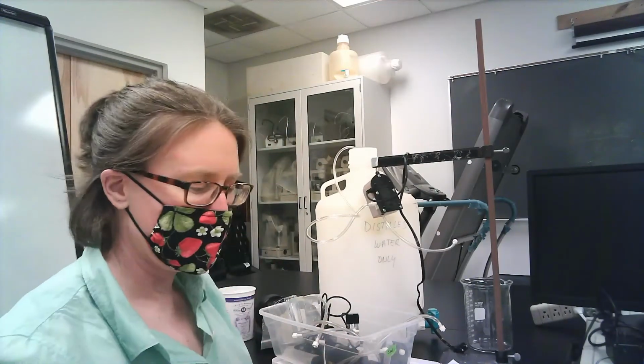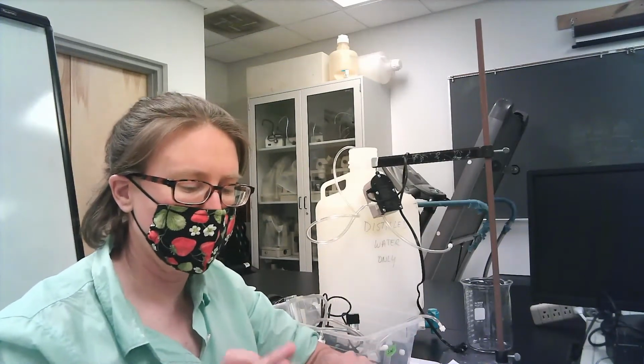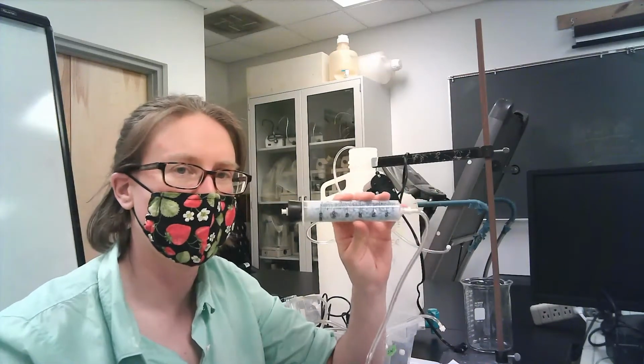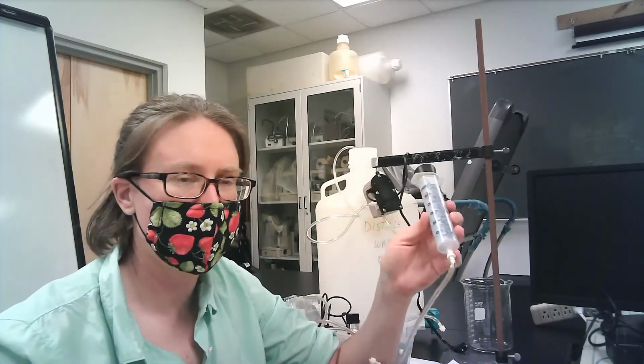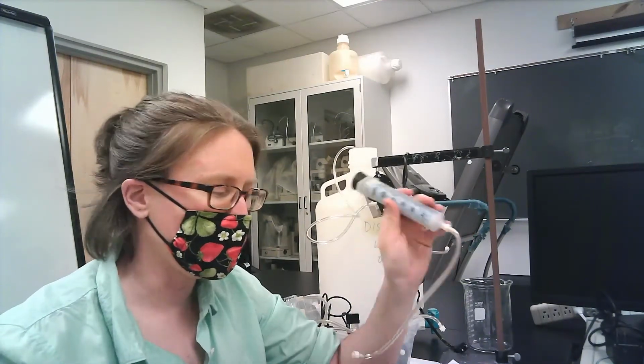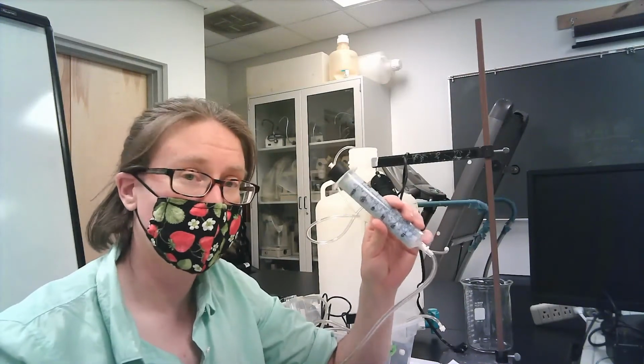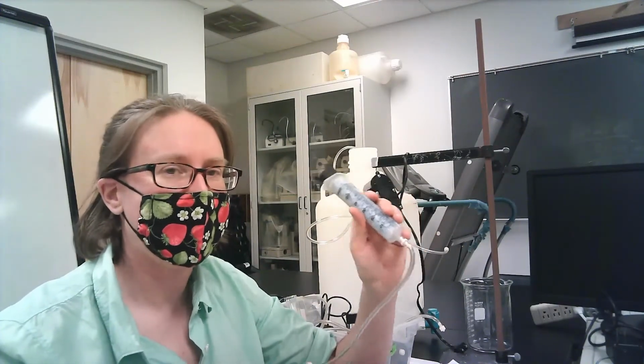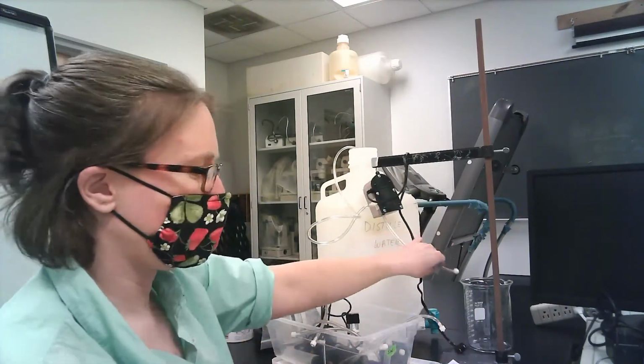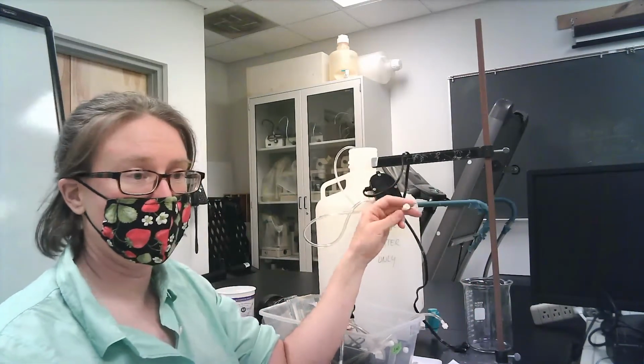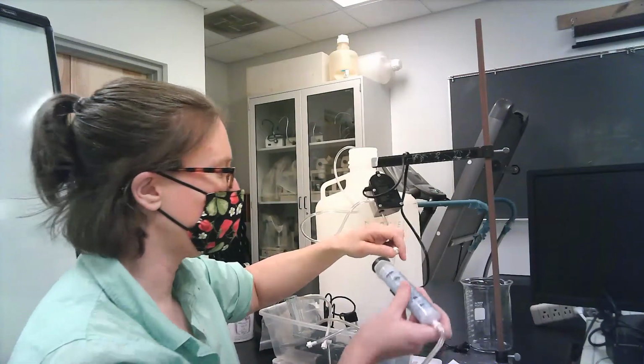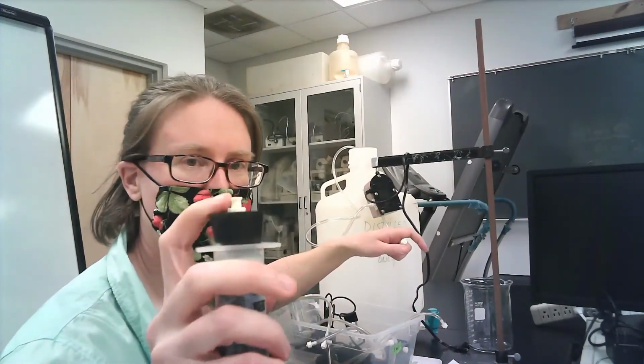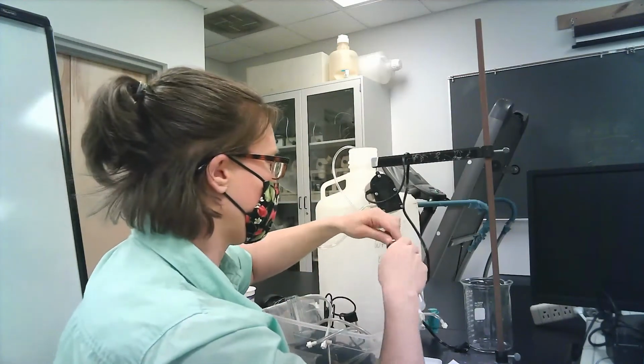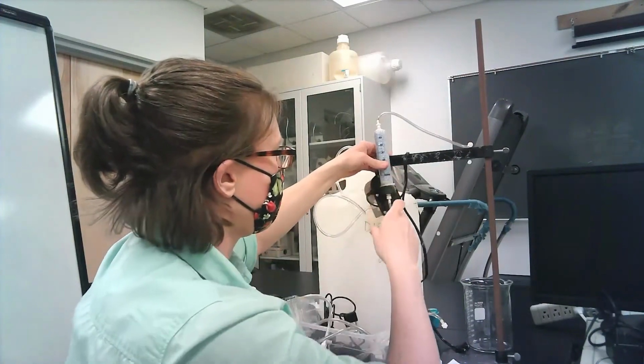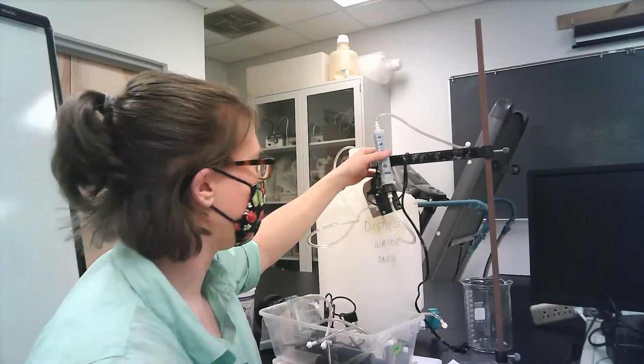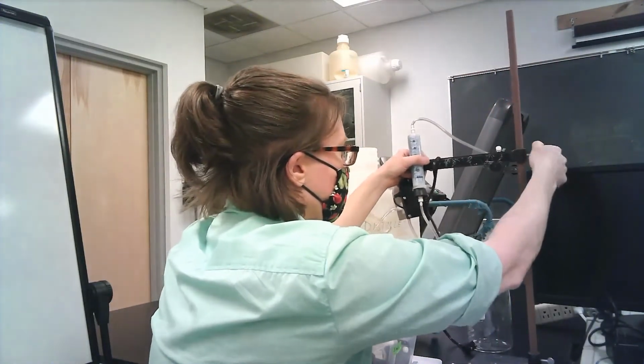To scrub out the water that's in the air, we also have this set of scrubbing columns. The scrubbing column is filled with a substance referred to as Drierite that is very good at bonding with the water that's in the air. This Drierite is blue when it is dehydrated, and it will turn pink as it picks up water from the air. Once again, we've got a female connector here on this gas pump, and then there's a male connector end here on the scrubber column, and you can just twist those together, and that's got some Velcro on it to hold it in place. So we're going to then start scrubbing the water out of the air. I'm actually going to lower this stand a little bit.